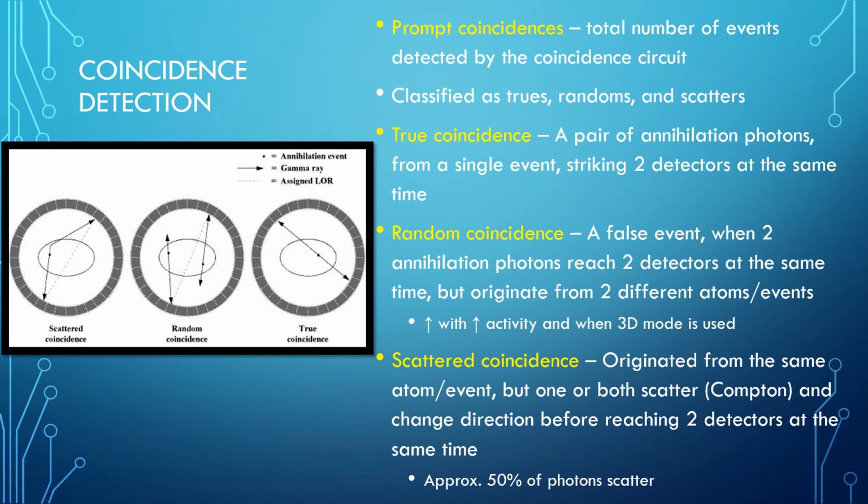So when you are scanning for PET CT, you inject that patient with a PET radiopharmaceutical inside their body. That positron decay happens, travels, and the positron will interact with an electron and have that annihilation event. And then the scanner is actually picking up those annihilation photons. As far as the instrumentation is concerned, those are called coincidences because they're looking at the photons that are arriving 180 degrees from each other, opposite detectors at the same time.